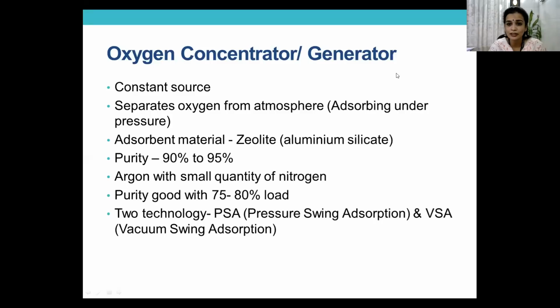It adsorbs the oxygen. The adsorbent material is silicate, the aluminum silicate. Purity cannot go beyond 95%. It is about 90 to 95%. What are the impurities that are present? Some argon and some amount of nitrogen. If you need to have good flow, then you can load the system only up to 75 to 80%. There are two technologies available.